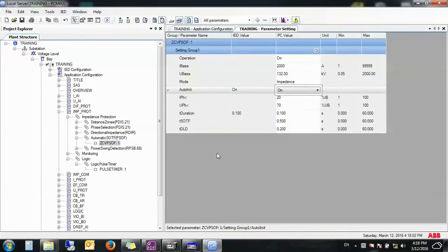Great. The certain period of time here is called T switch on to fault, but this is a drop-off time delay, which means after it goes, it counts 500 milliseconds and then sets it to 0. So if a manual close command comes and then it was 0, it doesn't consider it 0. It considers it 0 until its duration, which is half a second. This means drop-off time, not on delay time, for example.